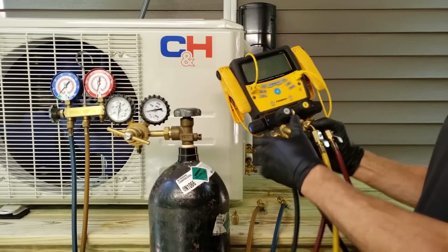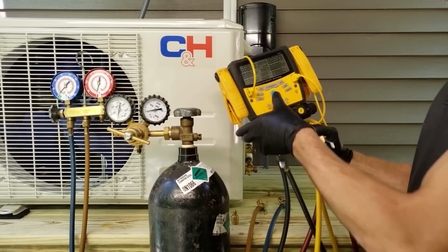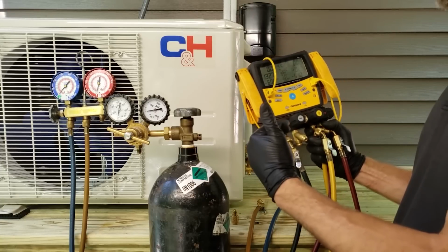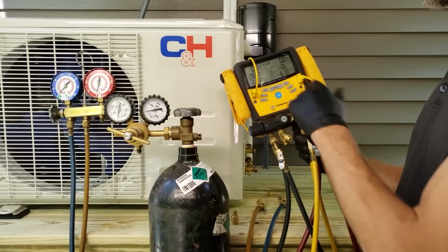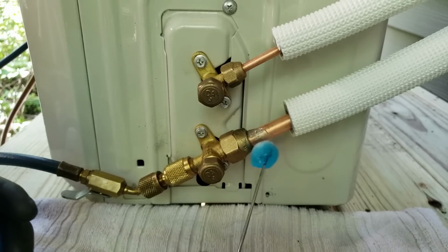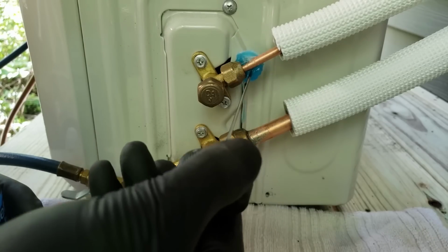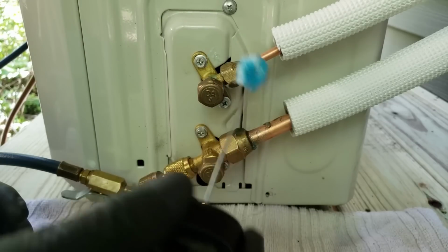Yeah. Absolutely. And to your point with pressure testing, I always recommend digital gauges, either probes, wireless probes, or just digital in general, because it's very important. You'll see the pressure drop real quickly instead of with a compound gauge where you have to wait a longer period of time. Likewise, though, with a used system, you don't want to pressurize it too high because you could make a leak. It's kind of that old situation we had with the old R22 coils. When you're pressure testing it, you can make a leak instead. So the digital pressure readout is going to give you a quick turnaround time as far as if you have a leak or not, and use non-corrosive bubble leak detector on the joints. Anytime I pressure test, I always put the non-corrosive bubble leak detector on those joints to see if I see any glistening whatsoever, and absolutely, that's what you want to do.